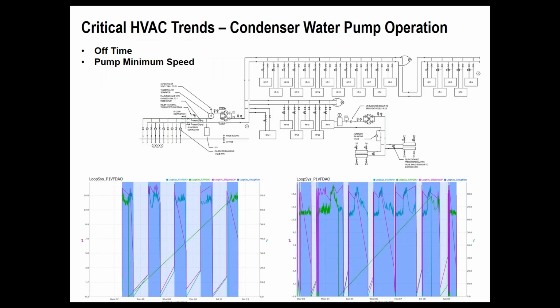Which brings us back to some of our energy savings assumptions and evaluation. What we can see here is a couple of graphs. The important thing to understand is that we're looking at the condenser water pumps, which are really part of the heart of the whole system. So, as I went through functional testing, bringing in some of those assumptions from the energy model into things that I was verifying during functional testing on site, something as simple as pumps literally turning off.